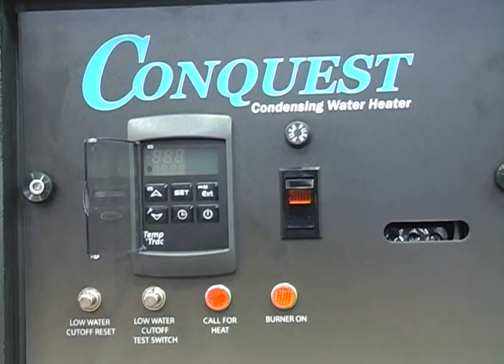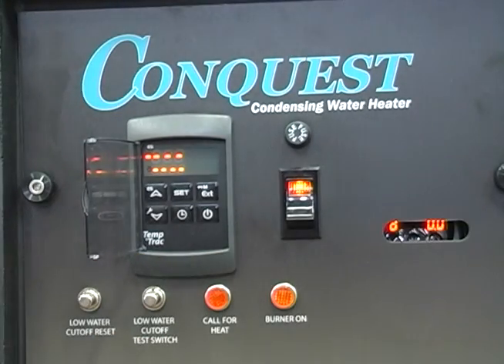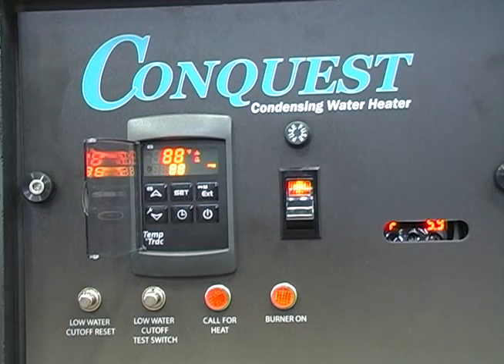Turn the water heater on using the electrical rocker power switch on the front of the control enclosure. The display on the Temp Trac electronic operating control and the on-off switch should both illuminate. The water heater control will sense the low water temperature in the tank and begin a trial for burner ignition. The start for a call for heat will be indicated on the Temp Trac operating control by illumination of the flame icon. The call for heat light on the control panel will illuminate shortly after the trial for ignition begins.